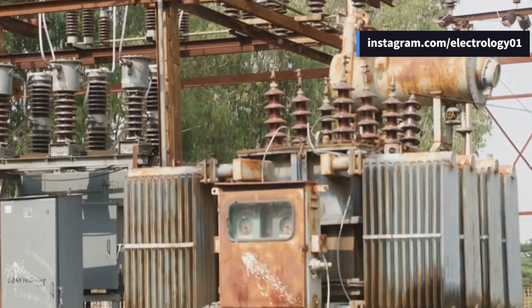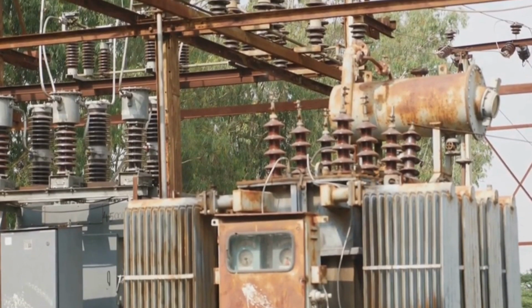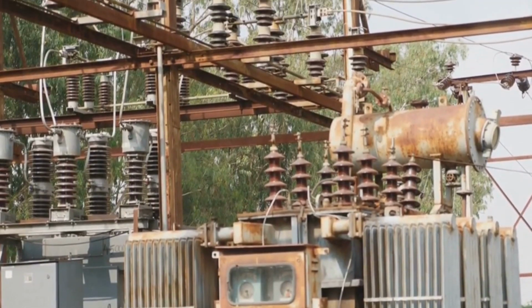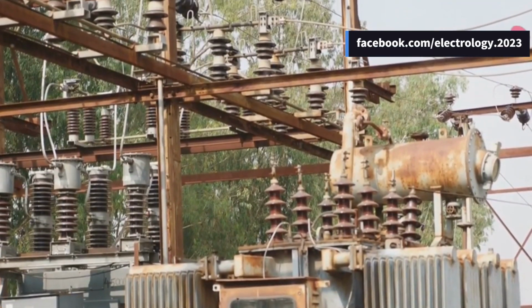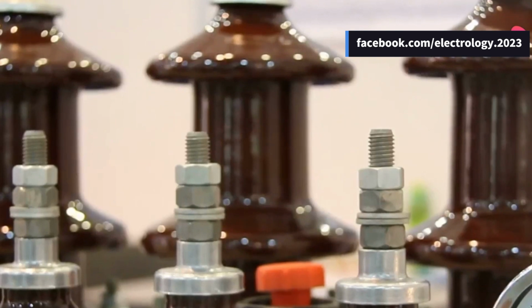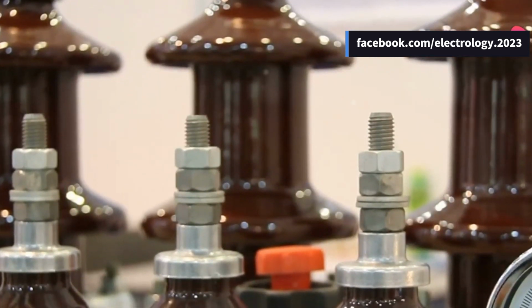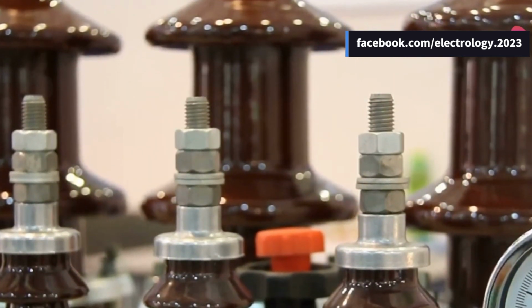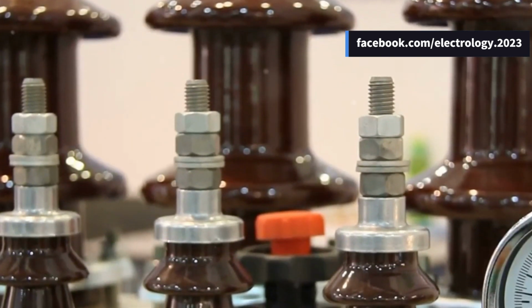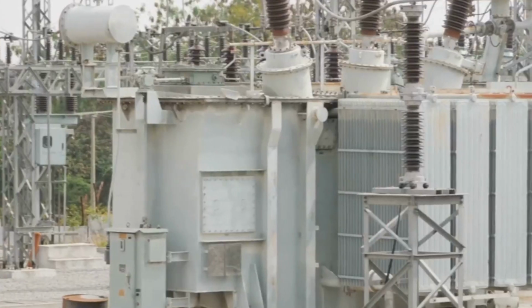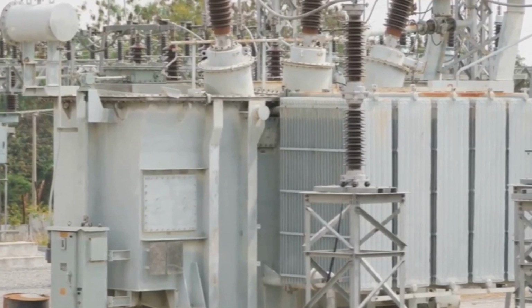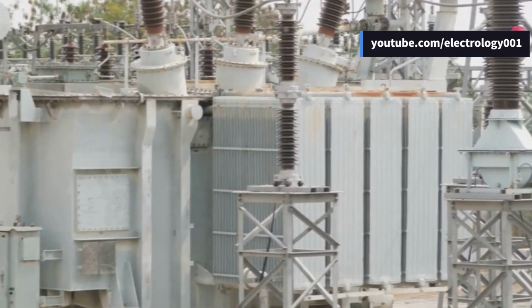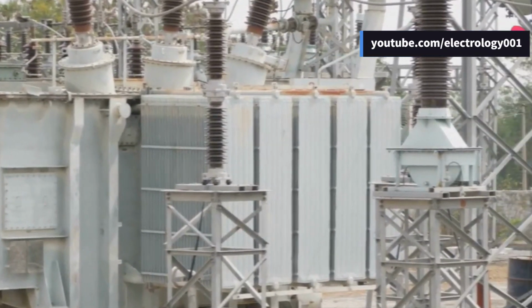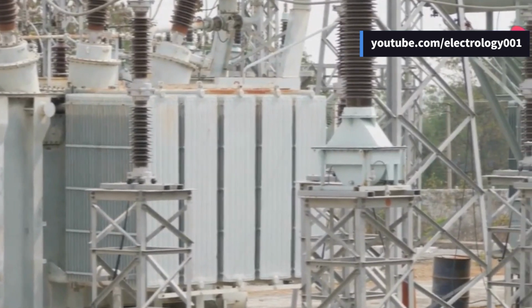Next, we have the percentage impedance. The current shared by two parallel running transformers should be proportional to their MVA ratings. Simultaneously, the current carried by these transformers is inversely proportional to their internal impedance. This means that the impedance of parallel running transformers should be inversely proportional to their MVA ratings. In other words, the percentage or per unit impedance values should be the same for all parallel running transformers.